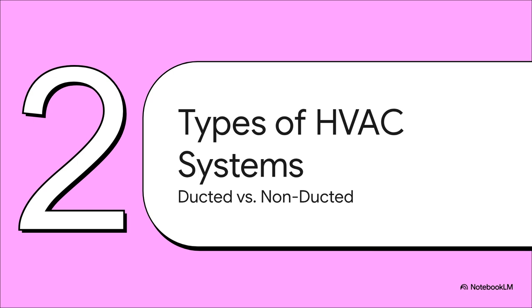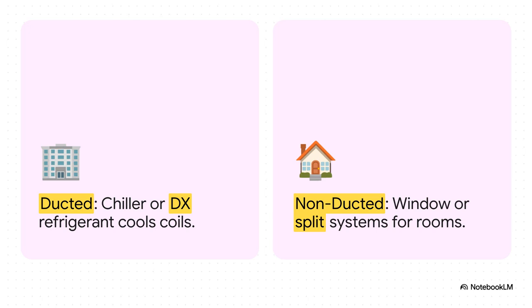Moving on to Section 2, Types of HVAC Systems, Ducted versus Non-ducted Architecture. Okay, let's zoom out a bit. In pharma, HVAC architecture is fundamentally divided. You have your massive, facility-wide ducted systems, which come in two main flavors. First is the chilled water system, where a chiller cools water that's then piped all the way across the facility to the air handling unit for heat exchange. Second is the direct expansion, or DX system, where refrigerant circulates directly inside the cooling coils. Now, on the other end of the spectrum, we have smaller, localized, non-ducted systems. This includes standard window systems packed into a single box for one room, and split systems, which separate the indoor cooling coil from the outdoor compressor. But for large-scale pharma production, those big ducted systems are the absolute heavy lifters.